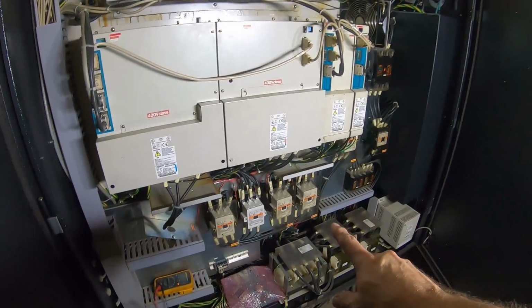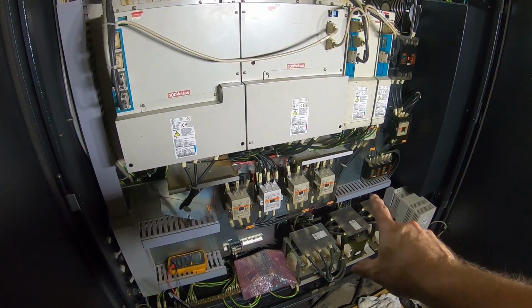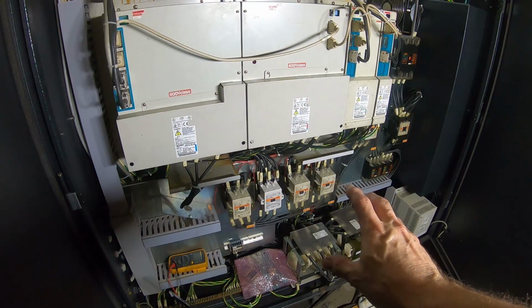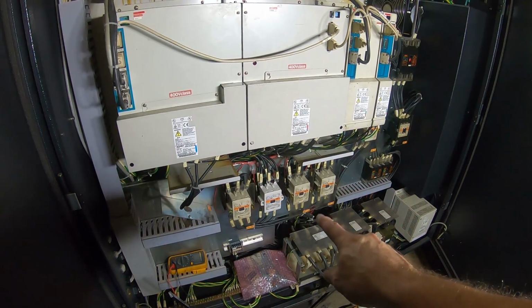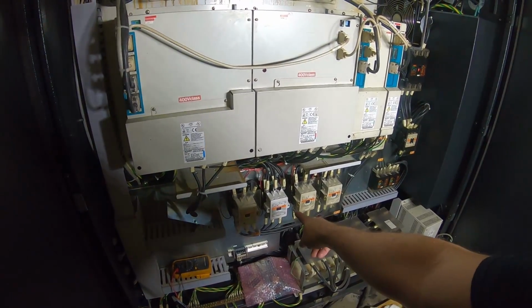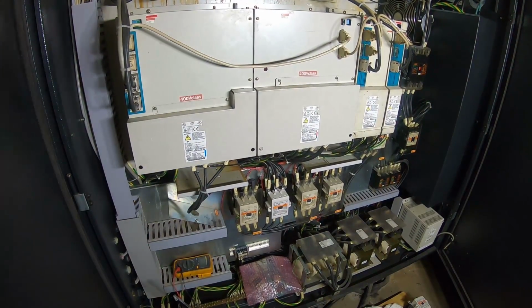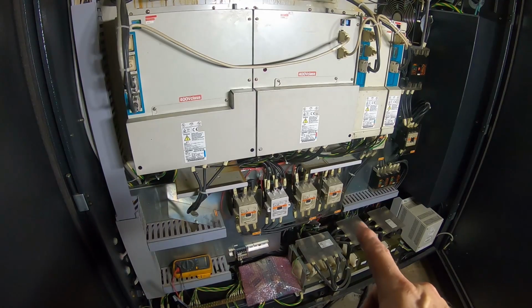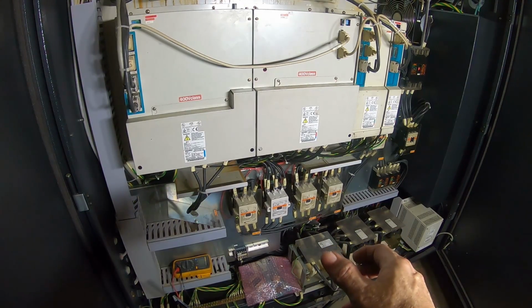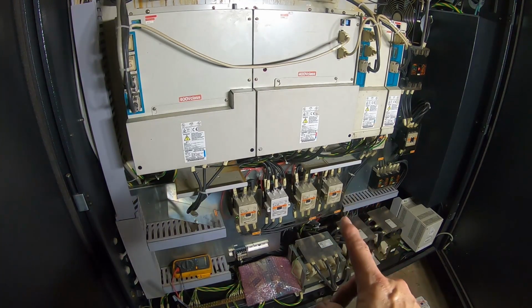Those relays down here control the winding directions in the motors, the spindle motors, depending on the speed. And this one here, uncovered at the moment, is the one I had to change out. That has to do with the delta windings of the turning spindle.